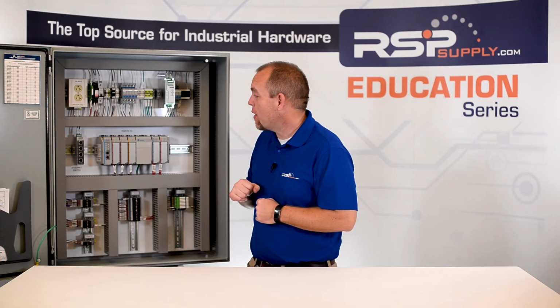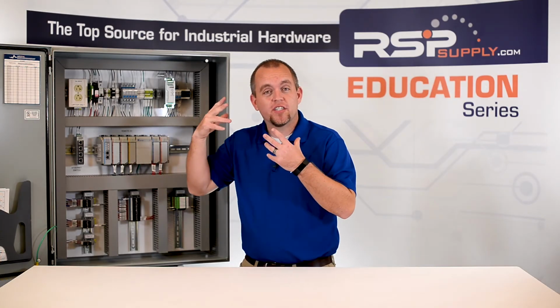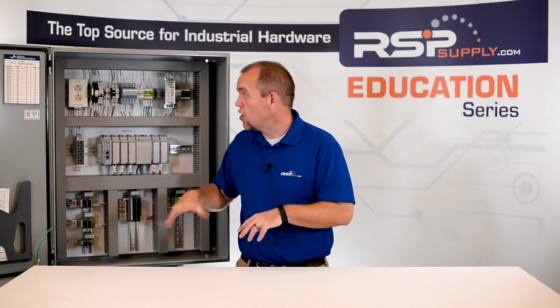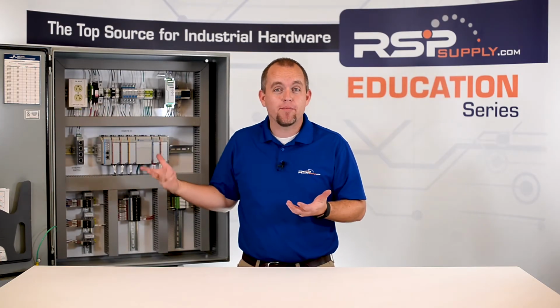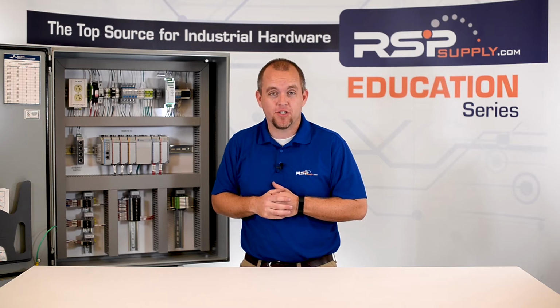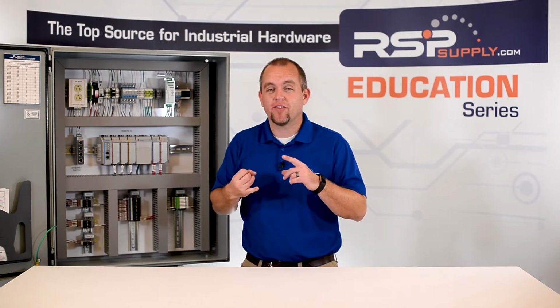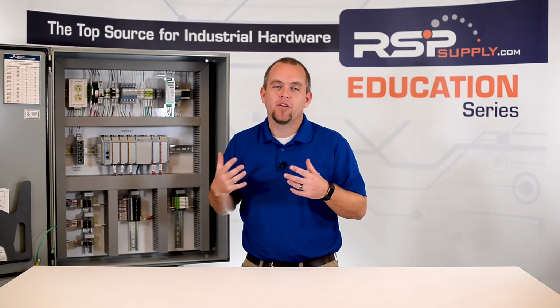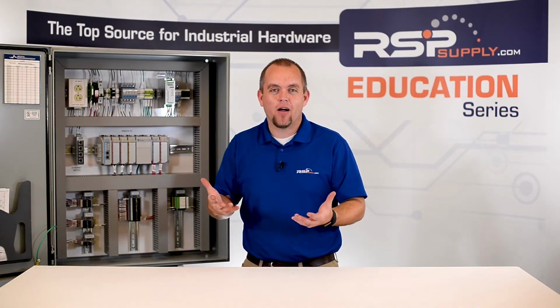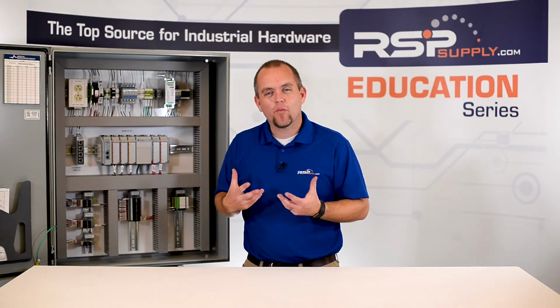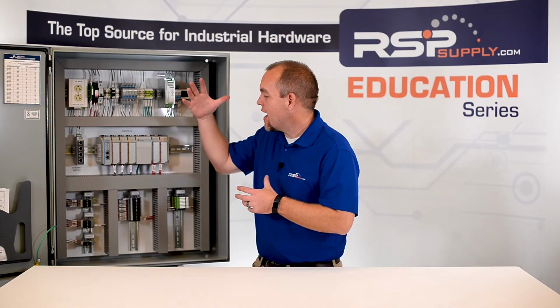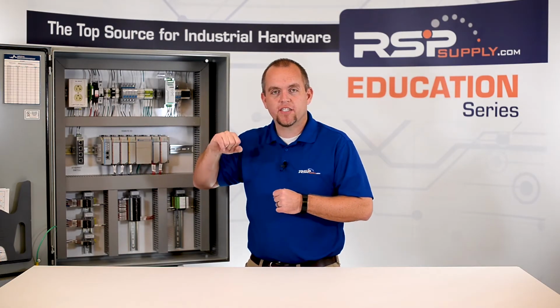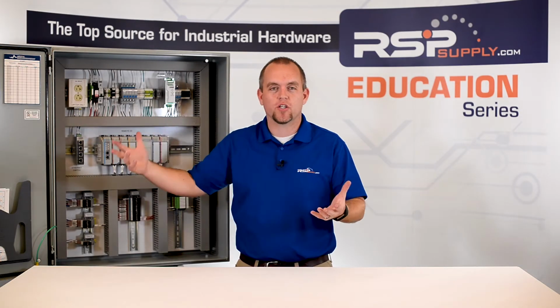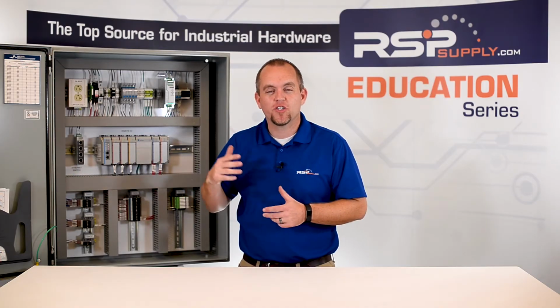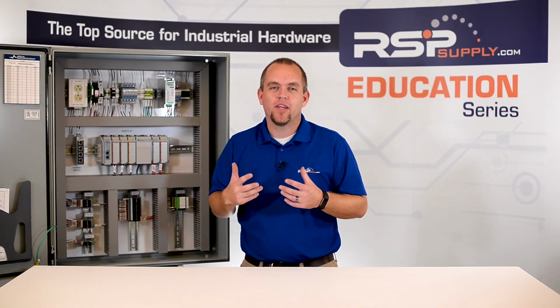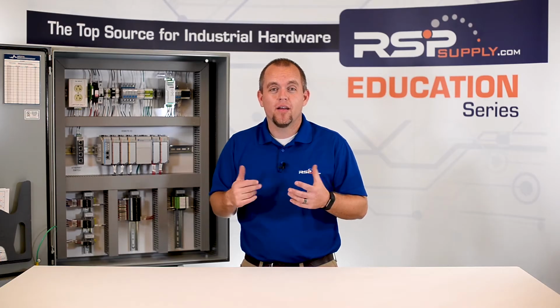This means that we would not want to use, for instance, a 2-amp fuse or breaker to protect an outlet that we might be plugging 15 or 20 amps into. That breaker or fuse would either continue to trip or blow, and we would not be able to use that outlet the way it is intended. Again, we would also want to not use a 15 amp breaker, for instance, to protect our PLC or a network switch. That can allow far too much current to run to those devices, allowing them to prematurely fail because of that excess current.